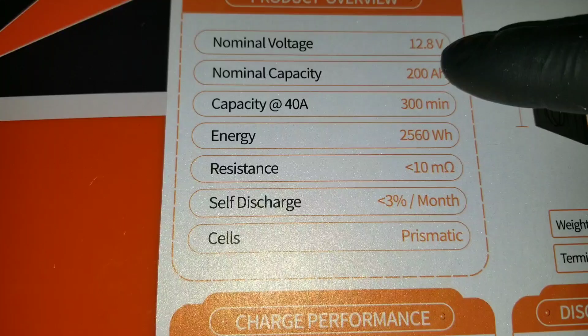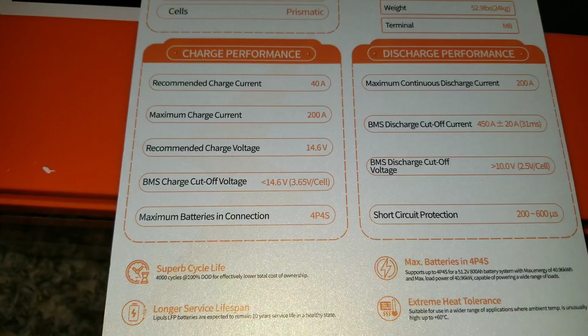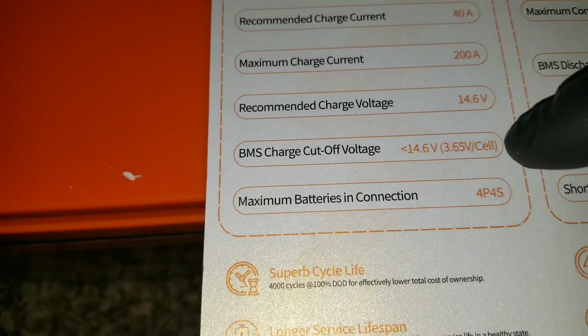So this is the charge, nominal voltage is 12.8, and you can charge this battery, I suppose, almost to 14.6, the max cutoff. Yep, right here, recommended charge voltage is 14.6. It's 200 amps continuous, the max charge current is the recommended. This is the max, this is when the battery is full, and the BMS cutoff voltage is at 14.6, which is 3.65 volts per cell.